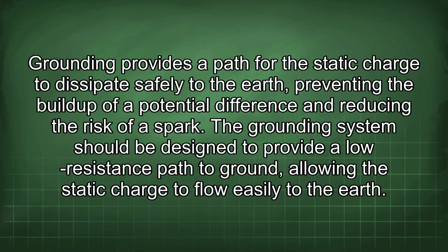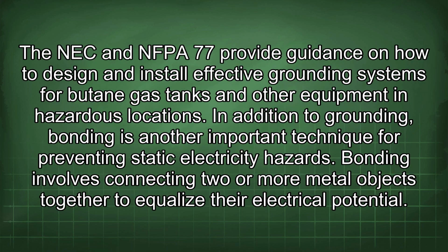Grounding provides a path for the static charge to dissipate safely to the earth, preventing the build-up of a potential difference and reducing the risk of a spark. The grounding system should be designed to provide a low resistance path to ground, allowing the static charge to flow easily to the earth. The NEC and NFPA 77 provide guidance on how to design and install effective grounding systems for butane gas tanks and other equipment in hazardous locations.